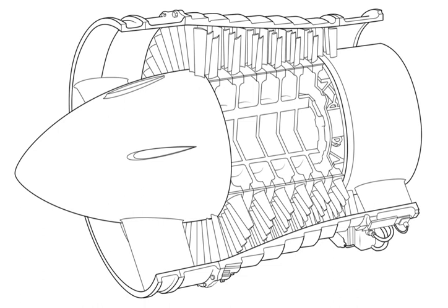Thus, a practical limit on the number of stages, and the overall pressure ratio, comes from the interaction of the different stages when required to work away from the design conditions. These off-design conditions can be mitigated to a certain extent by providing some flexibility in the compressor. This is achieved normally through the use of adjustable stators or with valves that can bleed fluid from the main flow between stages into stage bleed.